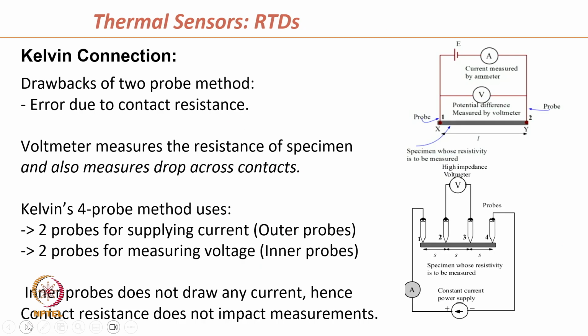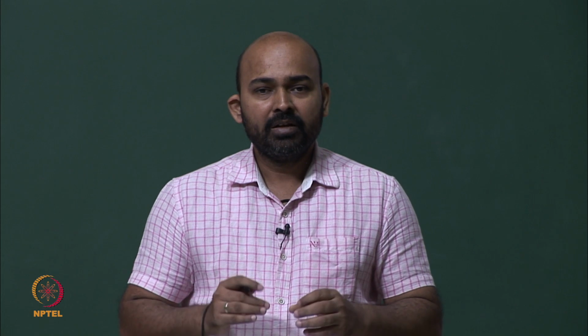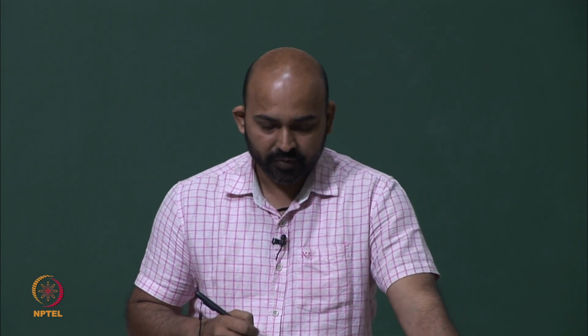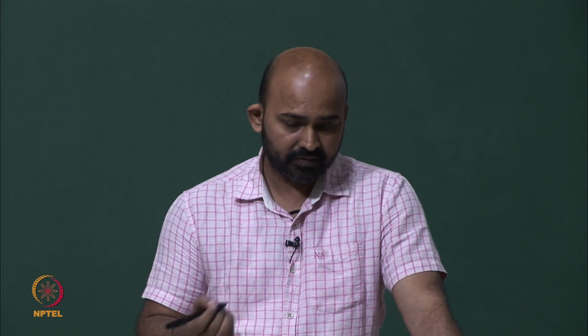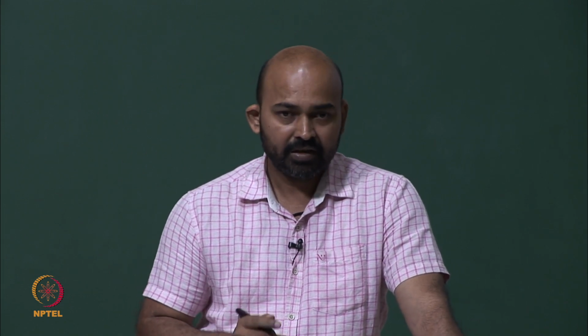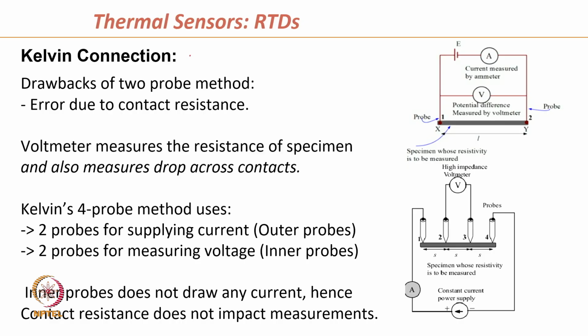So, this is what actually we are doing in this Wheatstone bridge example. We are doing a 4-point measurement instead of having a 2-point measurement. So, let us discuss what this 4-point resistance measurement is, or sometime we call it the Kelvin connection. This type of 4-point measurement is done for precise resistance measurement.